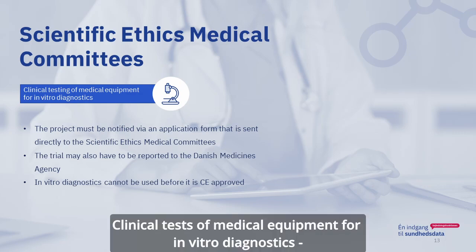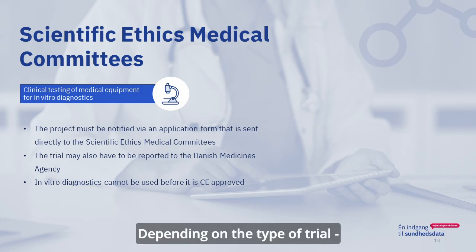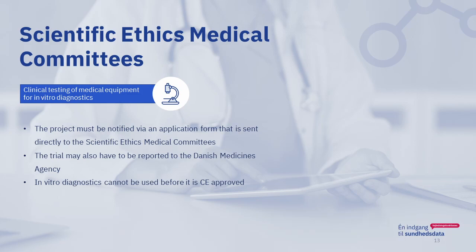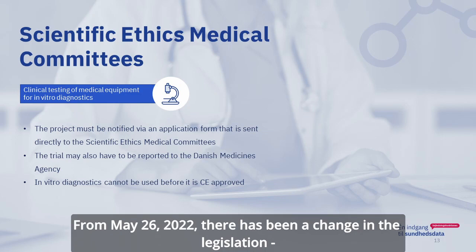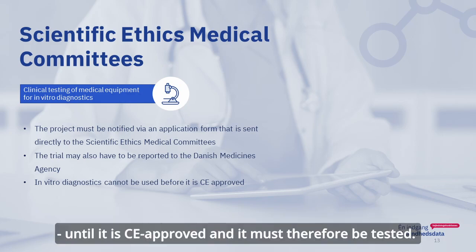Clinical testing of medical equipment for in vitro diagnostics must be reported via an application form sent directly to the Scientific Ethics Medical Committees. Depending on the type of trial, the trial may also have to be reported to both the Scientific Ethics Medical Committees and the Danish Medicines Agency. From May 26, 2022, there has been a change in the legislation which entails that equipment for in vitro diagnostics cannot be put into use until it is CE approved, and it must therefore be tested.